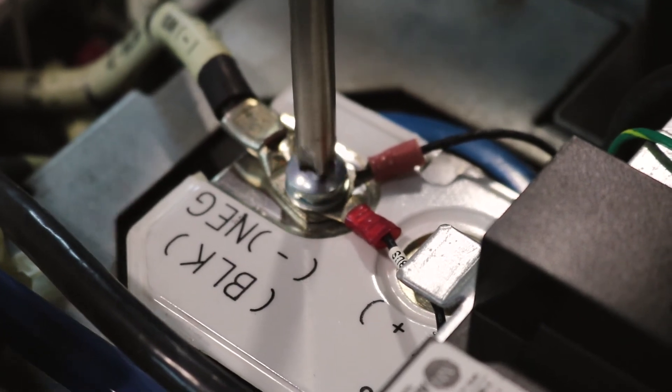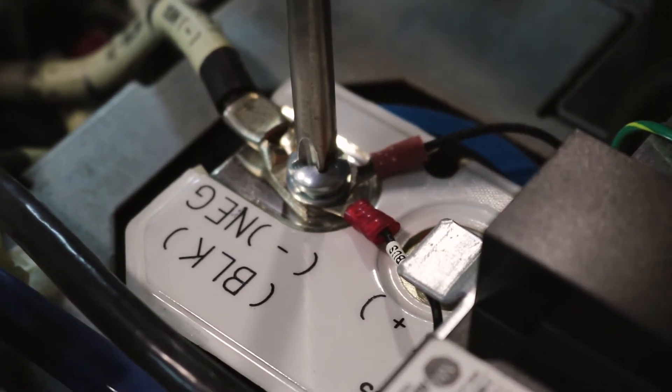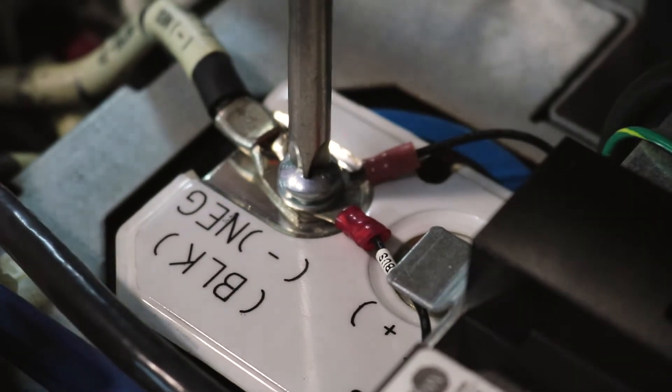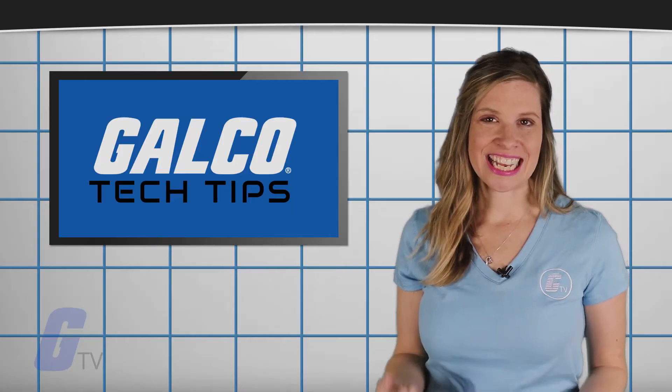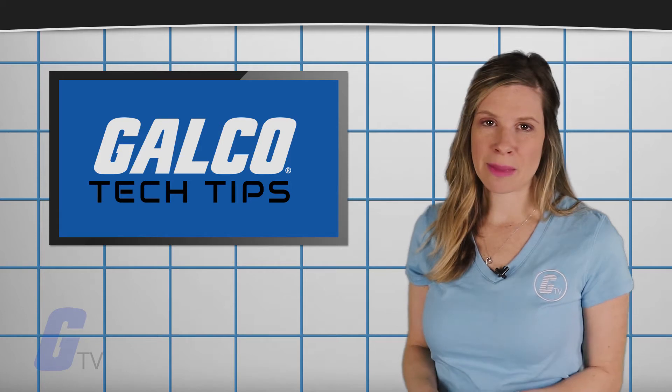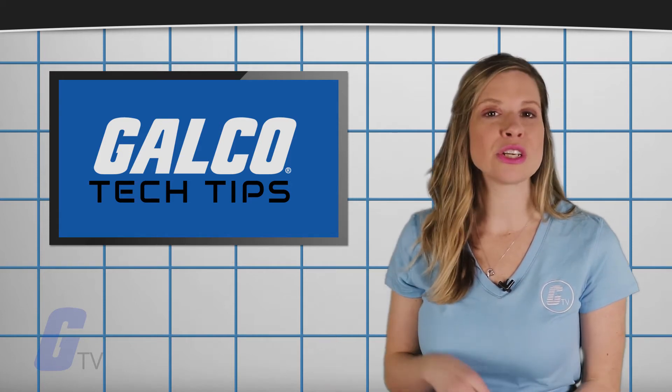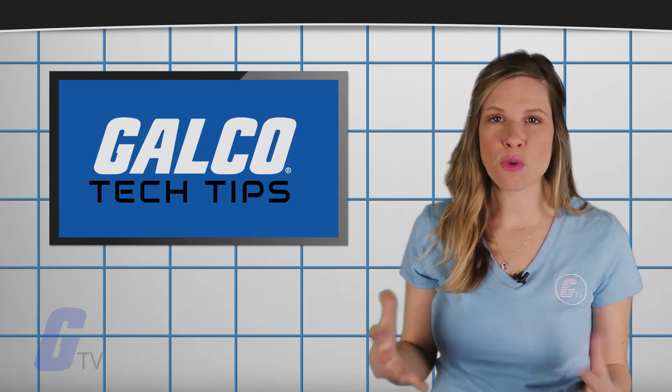Screws have a maximum clamping power at a torque value specific to its size, shape, and composition. Exceeding that torque value can permanently reduce the clamping power of that screw by reducing its elasticity and deforming it.